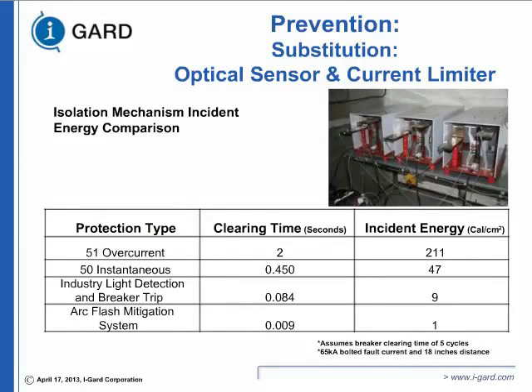Now you can see the comparison. If you're tripping with an overcurrent relay, your clearing time is 2 seconds, and your incident energy is going to be about 211 calories per centimeter squared. If you're tripping by instantaneous, you lose the coordination, and you're back to 47. If you use just optical detection, you still need to give the breaker tripping time; it's about 9 calories per centimeter squared. With the solid-state breaker, the total clearing time is about 9 milliseconds, 8 milliseconds for operation and 1 millisecond for detection, and you can cut down to 1 calorie per centimeter squared.